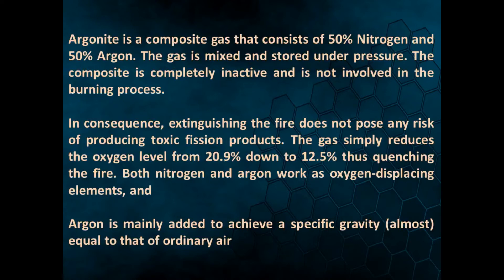Argonite is a composite gas that consists of 50% nitrogen and 50% argon. The gas is mixed and stored under pressure. The composite is completely inactive and is not involved in the burning process. In consequence, extinguishing the fire does not pose any risk of producing toxic fission products.